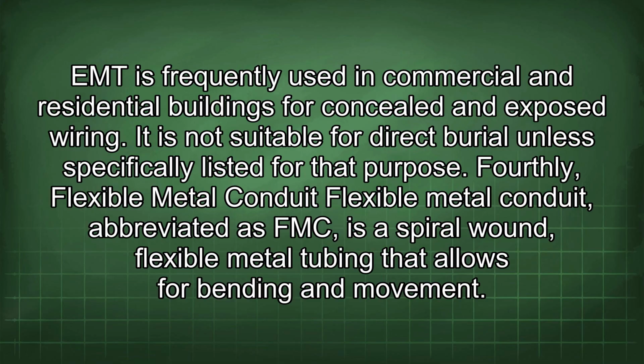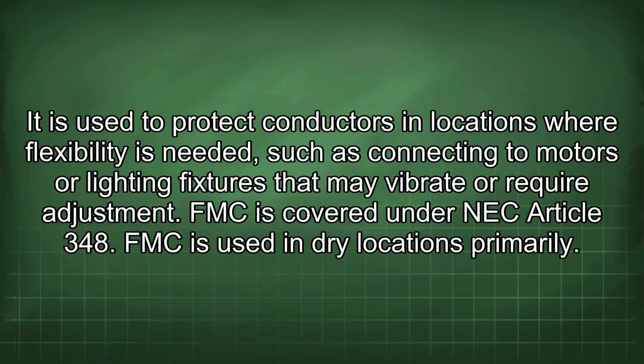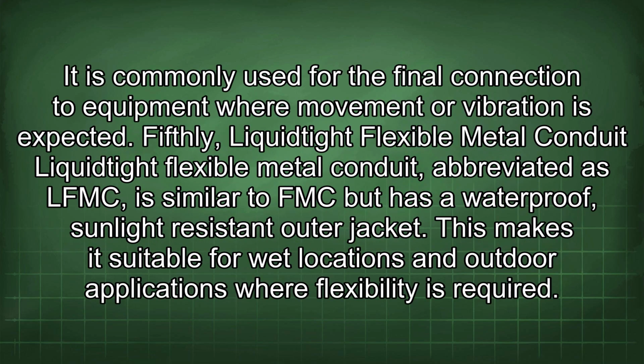Fourthly, flexible metal conduit. Flexible metal conduit, abbreviated as FMC, is a spiral wound, flexible metal tubing that allows for bending and movement. It is used to protect conductors in locations where flexibility is needed, such as connecting to motors or lighting fixtures that may vibrate or require adjustment. FMC is covered under NEC Article 348. FMC is used in dry locations primarily. It is commonly used for the final connection to equipment where movement or vibration is expected.